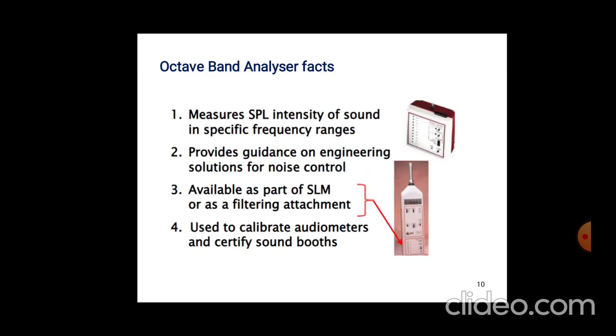The Octave Band Analyzer measures the sound pressure level (SPL) and intensity of sound in specific frequency ranges. It provides guidance on frequency-based solutions for noise control. It is available as part of an SLM or as a filtering attachment, and it is used to calibrate audiometers and certify sound booths. This covers all the basic noise measurement equipment.